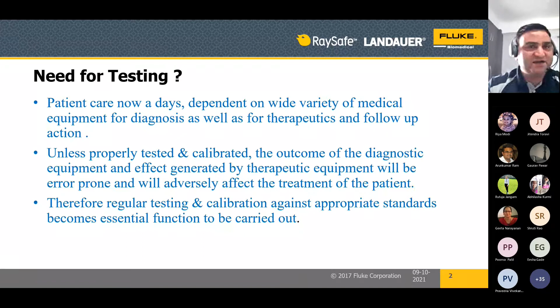But only by the feedback signal from the equipment, that blood pressure monitor, you are being treated by doctors. Sometimes, if that particular instrument is not tested properly, not calibrated, it can give any kind of result, whether good or bad. It can be bad also. And doctors have already started prescribing you medicines, which may or may not be required. That is why, unless properly tested and calibrated, the outcome of diagnostic equipments and the effect generated by therapeutic equipments will be error prone. It is always there. Therefore, regular testing and calibration is very important to do before you start any kind of procedure on the patient.